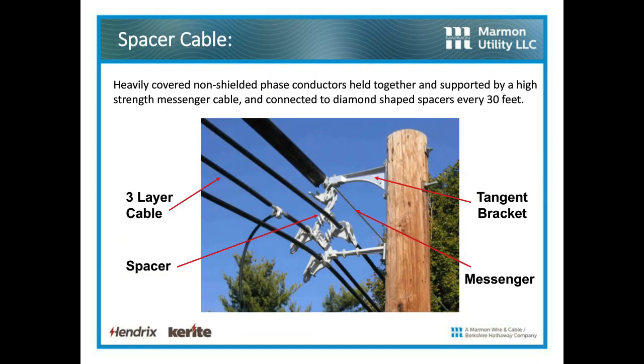If we look at the system itself, spacer cable is heavily covered non-shielded phase conductors, and they are held together and supported by a high-strength messenger cable. That messenger has 4 functions. It's the mechanical support member. It holds everything up in the air. It's the system neutral for systems connected in Y. It's a lightning shield, and mechanically, it holds everything off of that system that may fall onto it from above. You can see we've got a diamond-shaped spacer there at the pole. We have spacers every 30 feet.